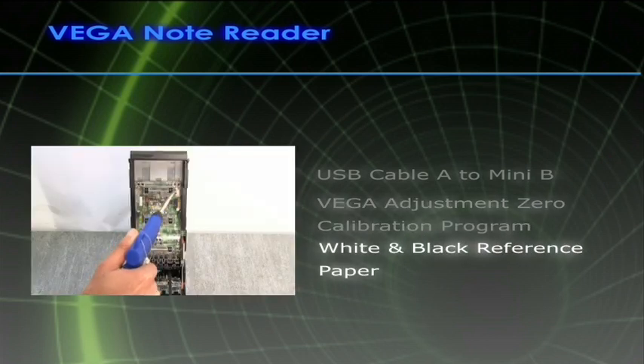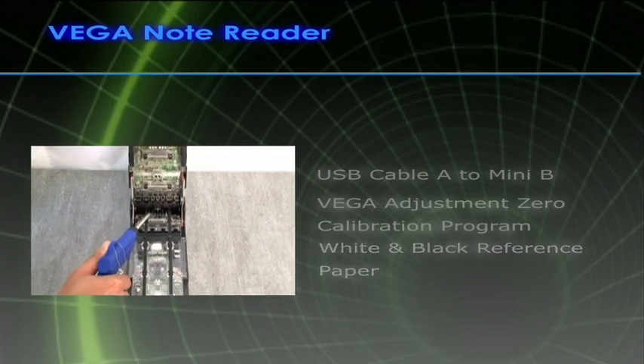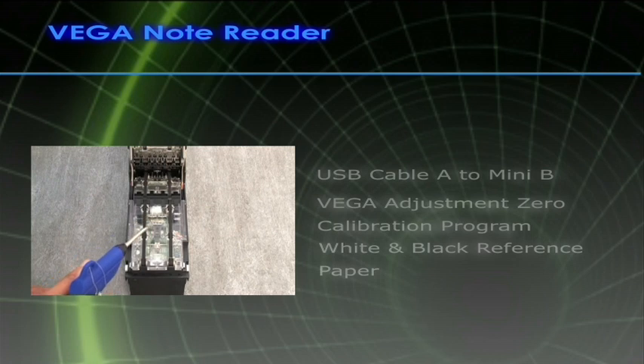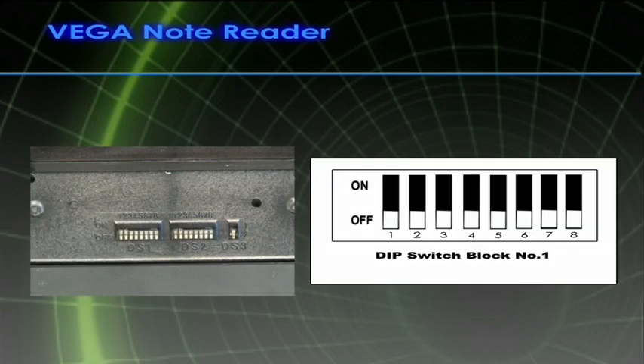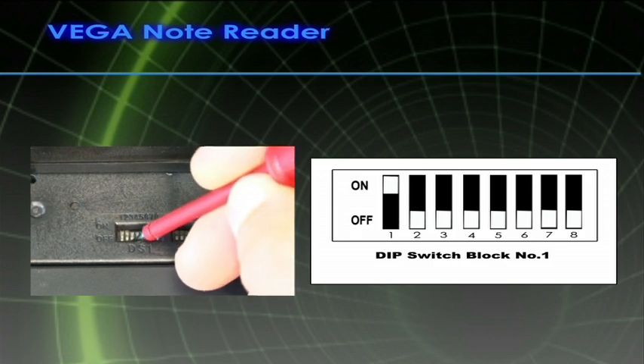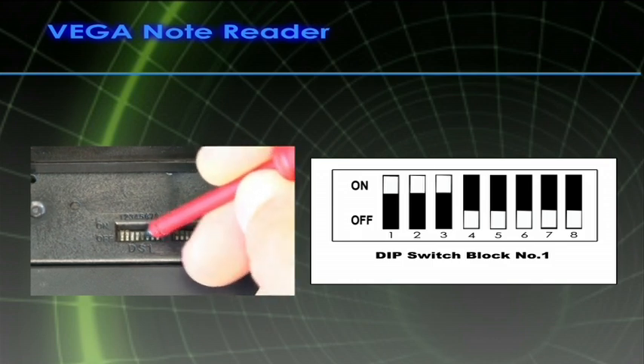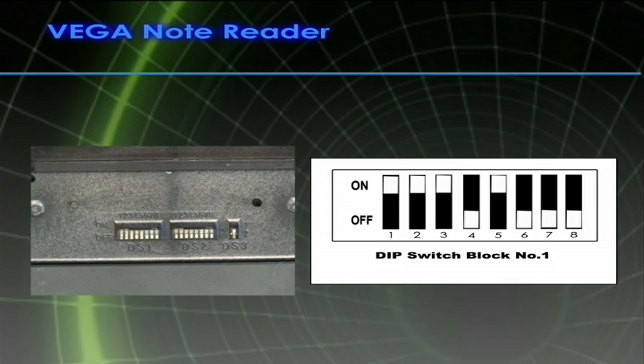Before performing a calibration procedure, be sure to clean the lenses of the Vega note reader. If any sensor is dirty, calibration will not be accurate. Set dip switch block number 1, switches number 1, number 2, number 3 and number 5 to on, and dip switch block number 2 switches all off.